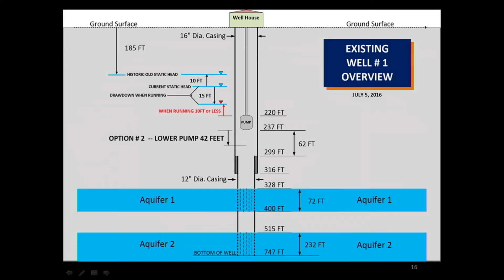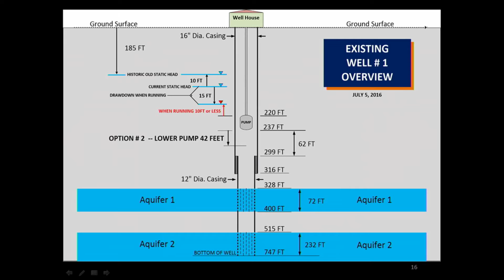And then we would size the pump to be able to pump a higher head, because it obviously has 42 feet more head than the existing pump. But we also want it to be able to pump all the way out to the Upper Mountain View pressure zone, because we want to get the water to the highest level of our system. And this actually, if this works, which it should, would eliminate the need for a booster pump station that was included in the design for well 5. So this is, like I say, a pretty attractive offer. And let me go into the next slide here.